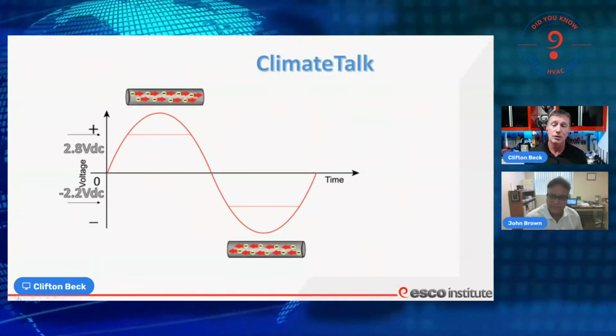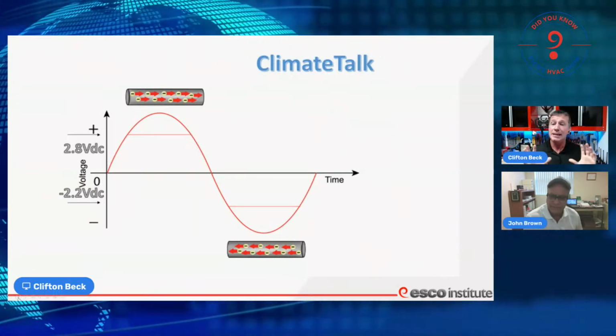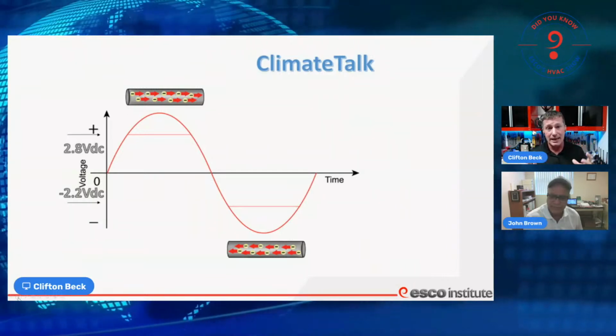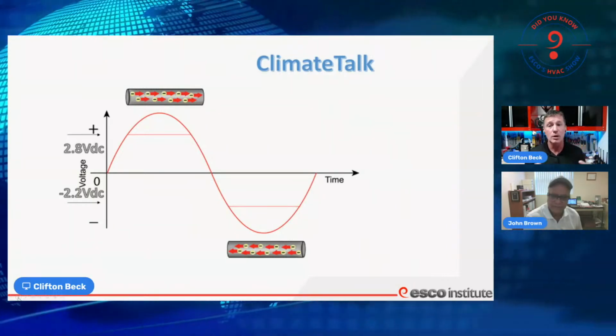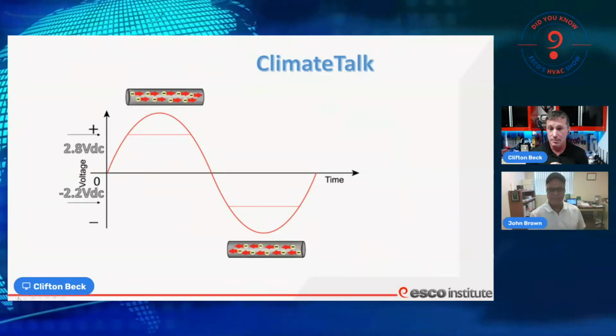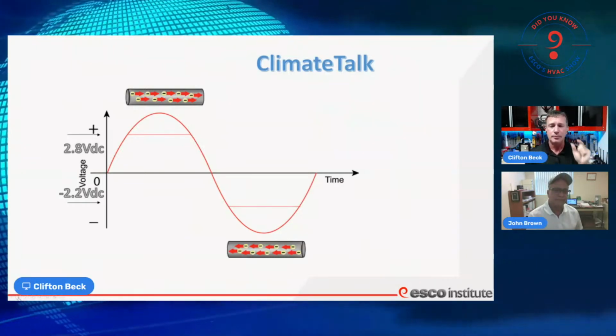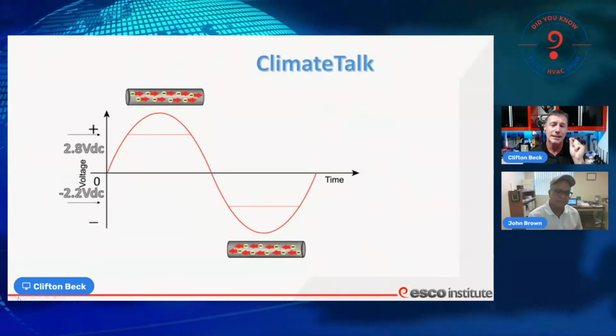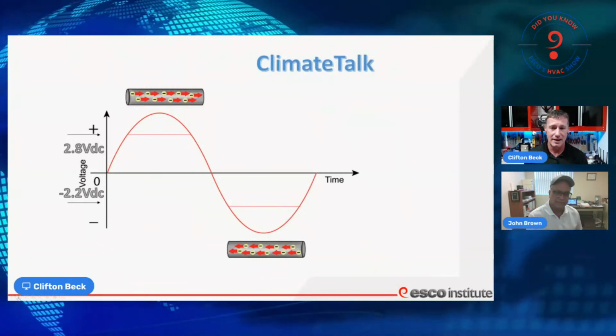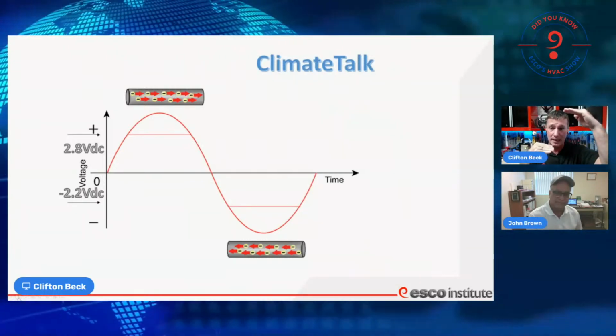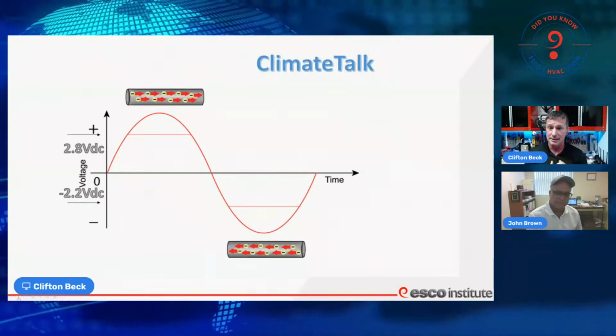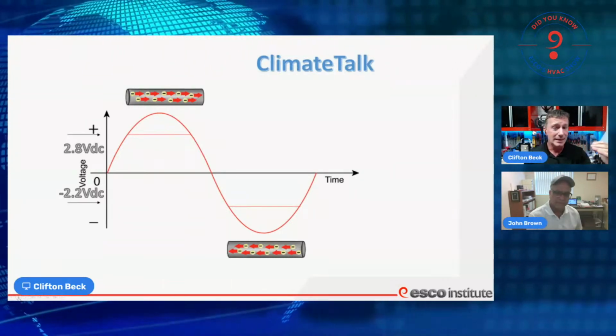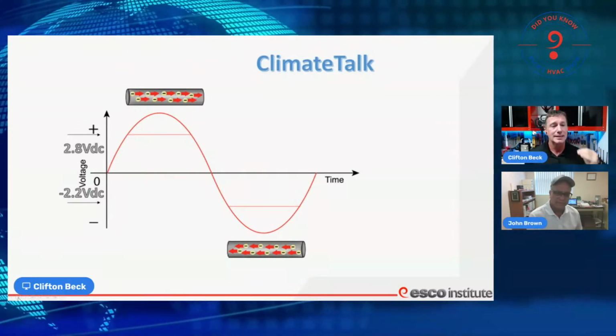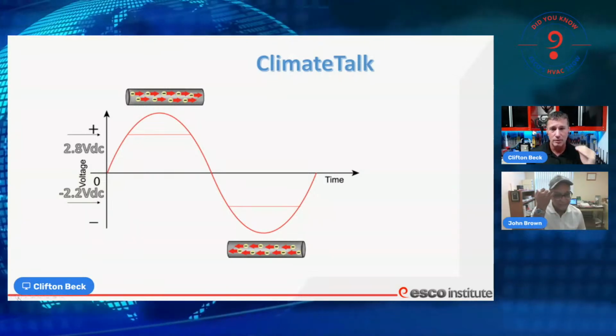Then we will add a grounded reference point to it. And the network that we're going to talk about today, which is the Climate Talk network — I would say that many manufacturers use this principle — we land that ground not exactly in the center of that 5-volt DC span. Remember, it's 5-volt DC, the height distance of our sine wave. We land it off center so that it is not directly in the middle of our reference point.